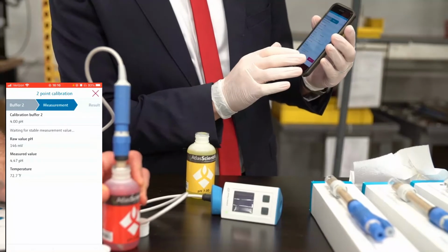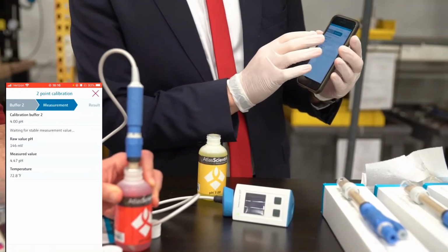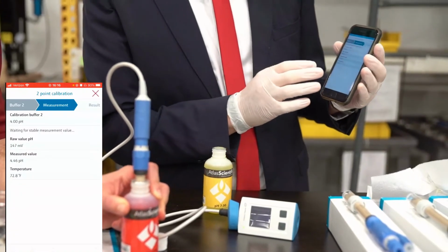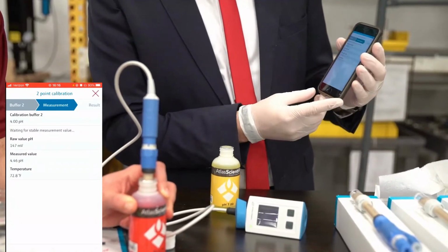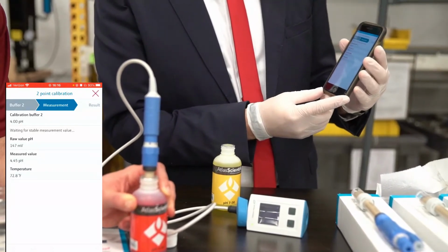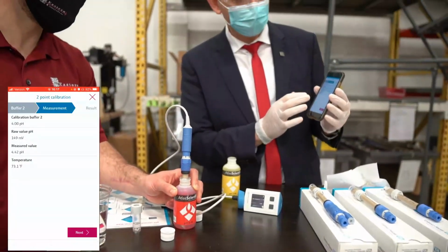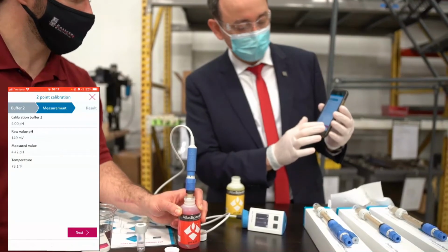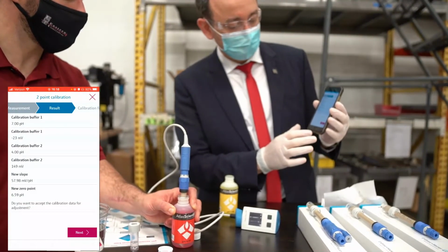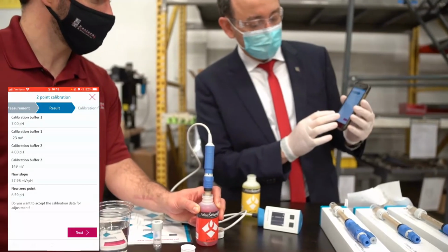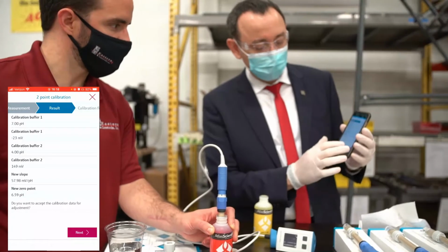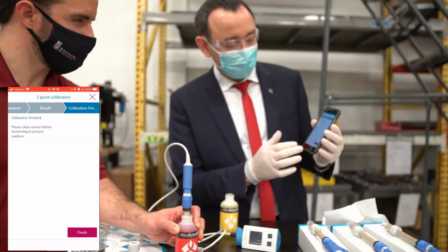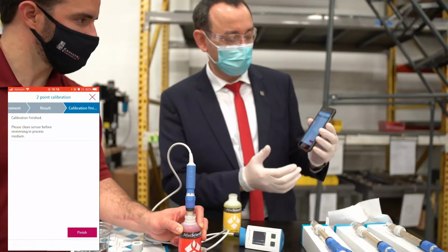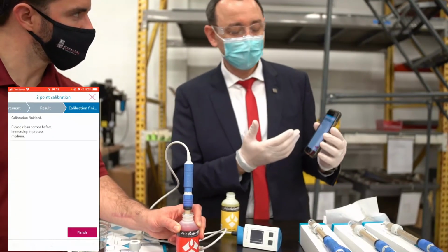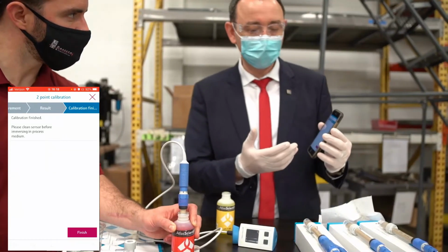So the next step is to immerse it in buffer 2. It is again waiting for a stable measurement in pH 4. It already knows that buffer 2 is pH 4. That is correct. It is automatically asking for that. So the calibration is finished after the second buffer, and we hit next. Now it is asking if we want to accept the new values, and I hit next, and it calculates a new slope and the zero point. Calibration is finished, and it says please clean the sensor before immersing into the process medium.